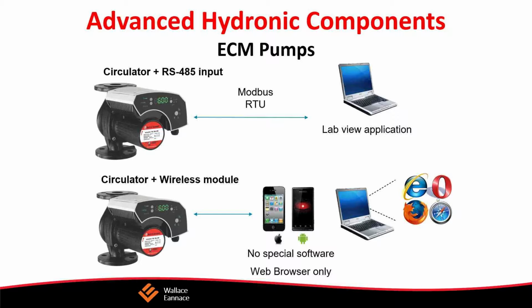Constant temperature. The pump will vary the speed to maintain temperature. It has an internal or external temperature sensor. In most cases, it already comes with an internal temperature sensor. You could add an external temperature sensor and program it to use that external temperature sensor. Or, as you'll see later on, you can actually have a delta T mode when you add the external temperature sensor. You can use constant temperature. It can be used to maintain zones supply water temperature. Not only that, it can also be used in potable applications as effectively as an aquastat.